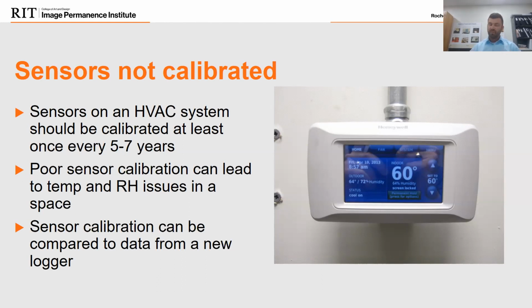We've worked with institutions that have never calibrated their sensors in 20 or 30 years of existence, still using the same sensors. And we've seen a circumstance where a sensor was 15 to 20 degrees out of calibration. If you ever want to check it, it doesn't hurt to get a brand new, recently calibrated data logger and put it next to the sensor. What does the logger read? What does the sensor read? What does your brand new calibrated logger think is happening? What does the sensor for the room think is happening? It's a way of checks and balances for your own space, for your own system.